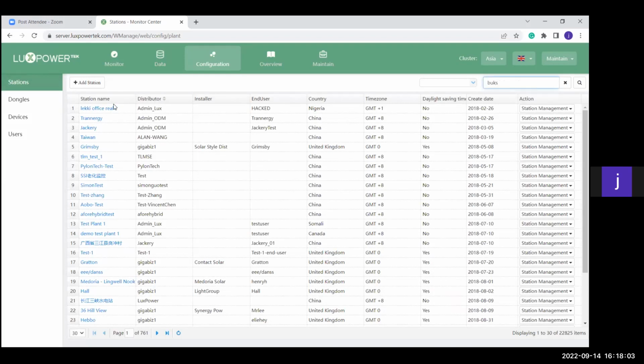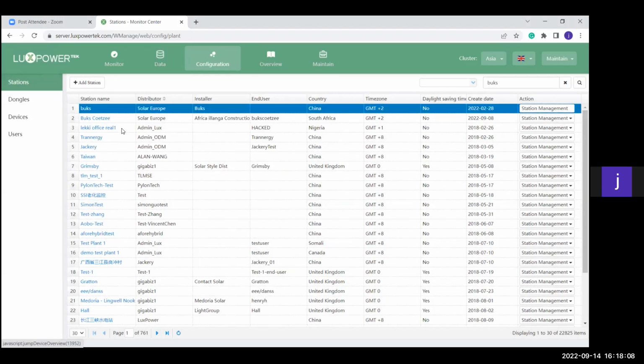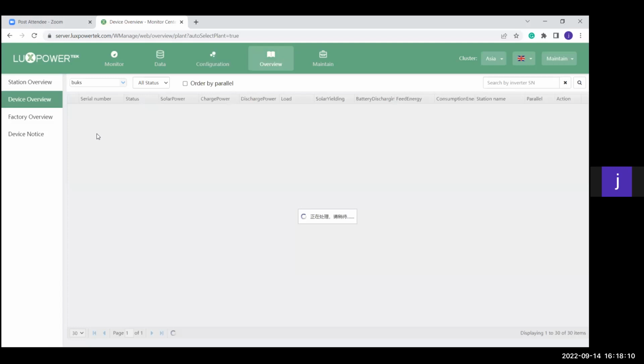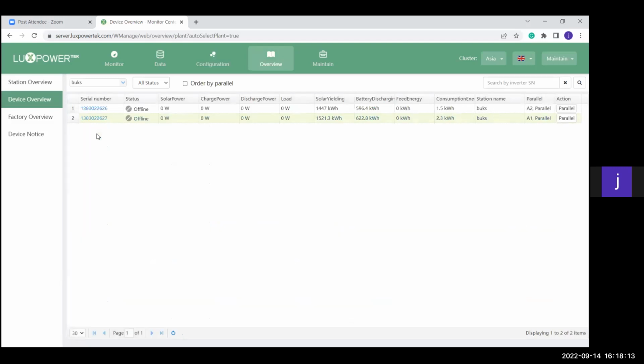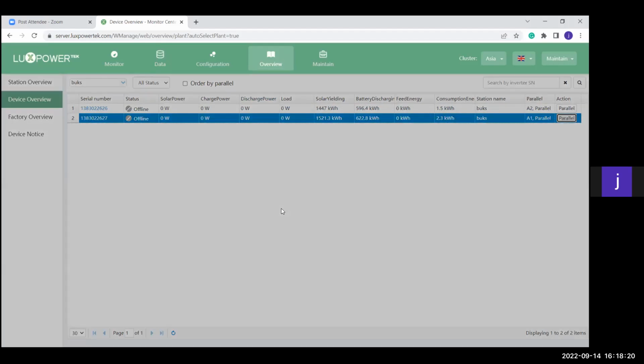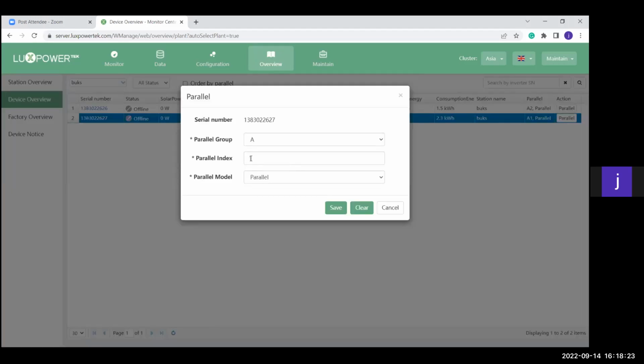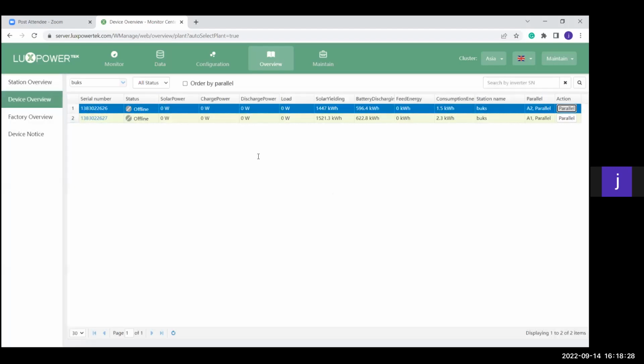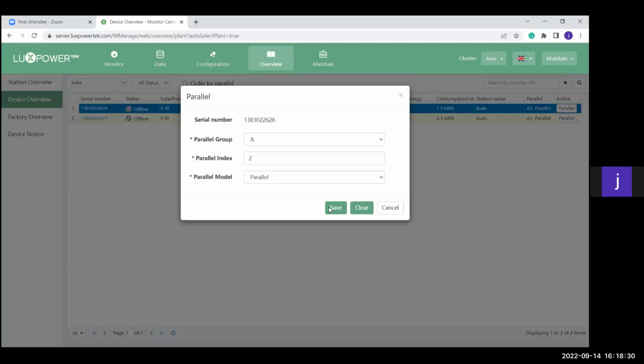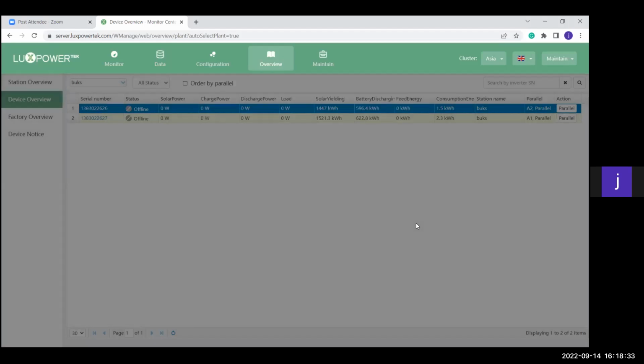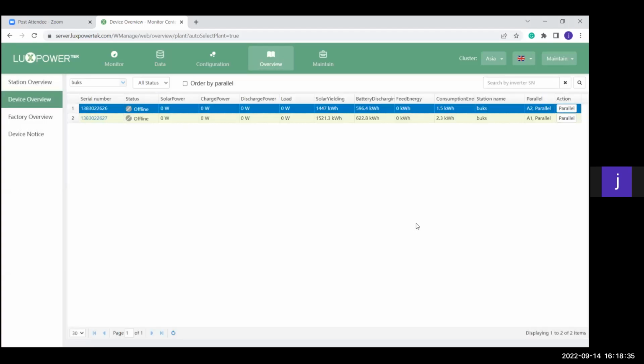So if we go back to his station, you will see he has added all his inverters to the same station. So here his 2 inverters are under the same station. Once you've added them under the same station, you will see the action on the side for parallel. So you go to the first one, you say parallel index, here it will be 0. You just type in 1, save, and then at the second one the same. You have parallel index, you type in 2, save.